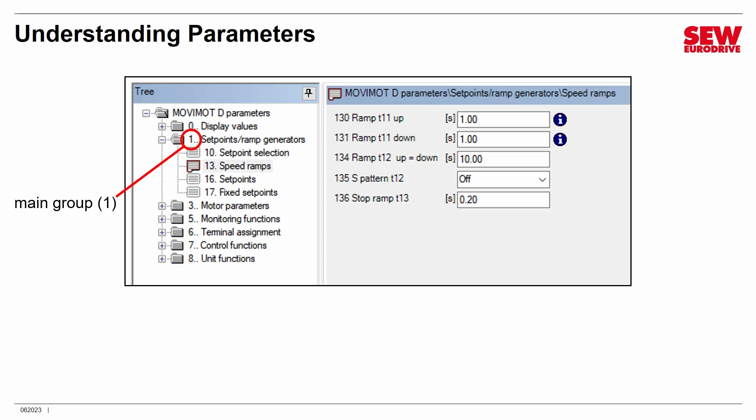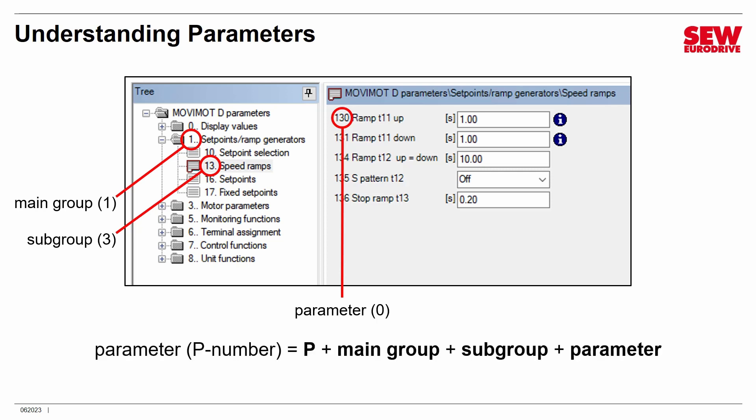Movimot has seven major parameter groups numbered 0 through 8, with some missing numbers in that range. These numbers identify what is called the parameter's main group. For example, 'setpoints and ramp generators' is group number 1. Underneath that group are additional groups and individual parameters. The second digit is the subgroup — for example, speed ramps are in subgroup 3, which is part of main group 1. The third digit is the actual parameter number. So for ramp T11 up, the parameter number is 0. The full identifier is parameter 130, or P130.